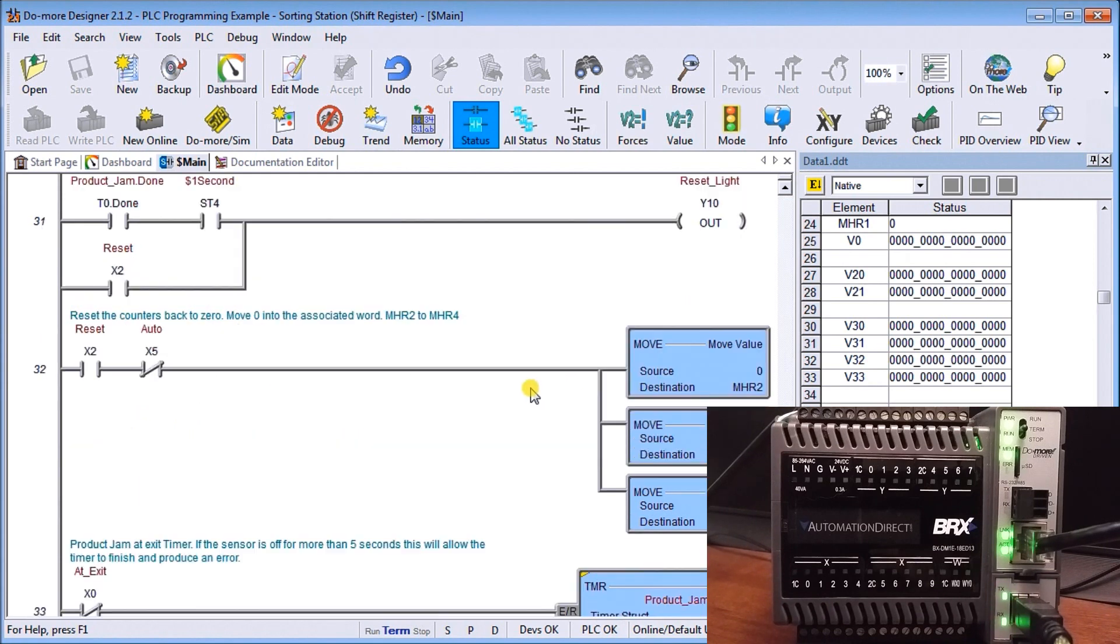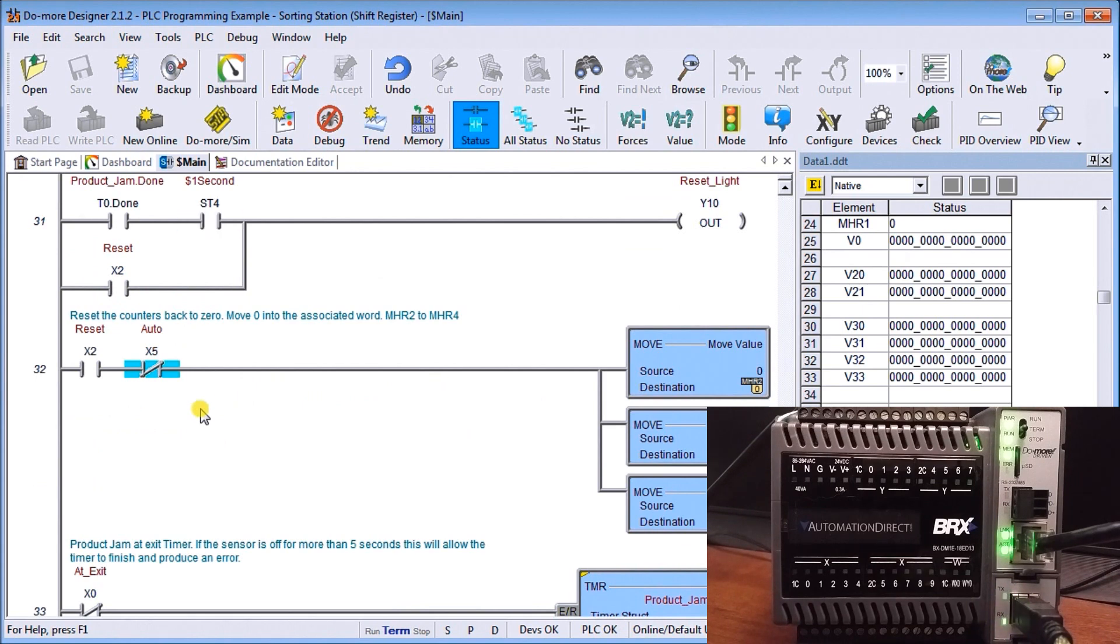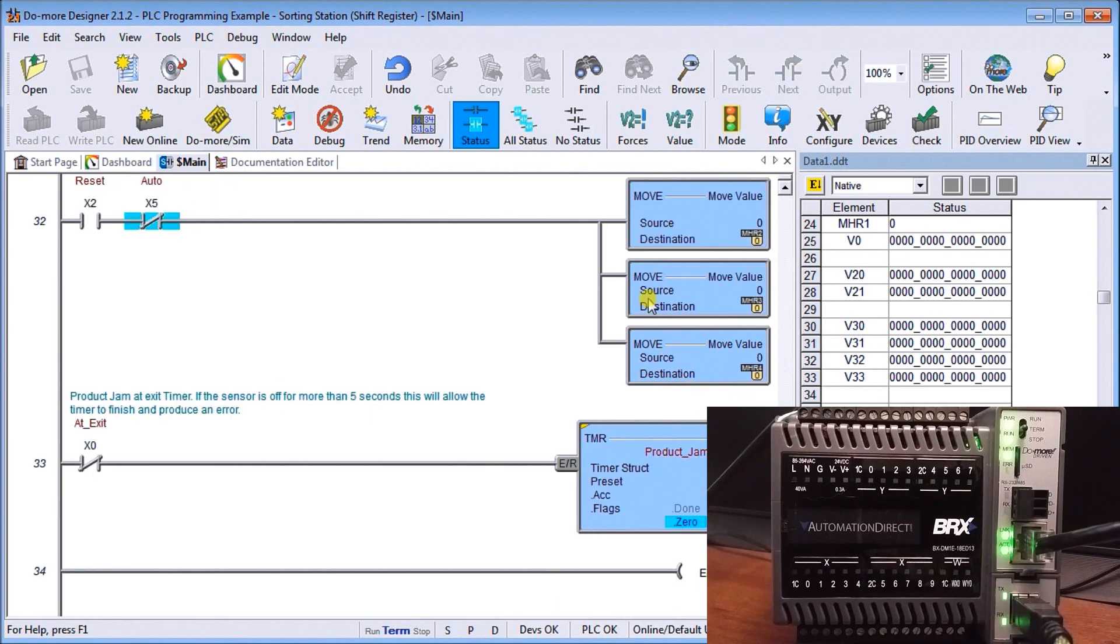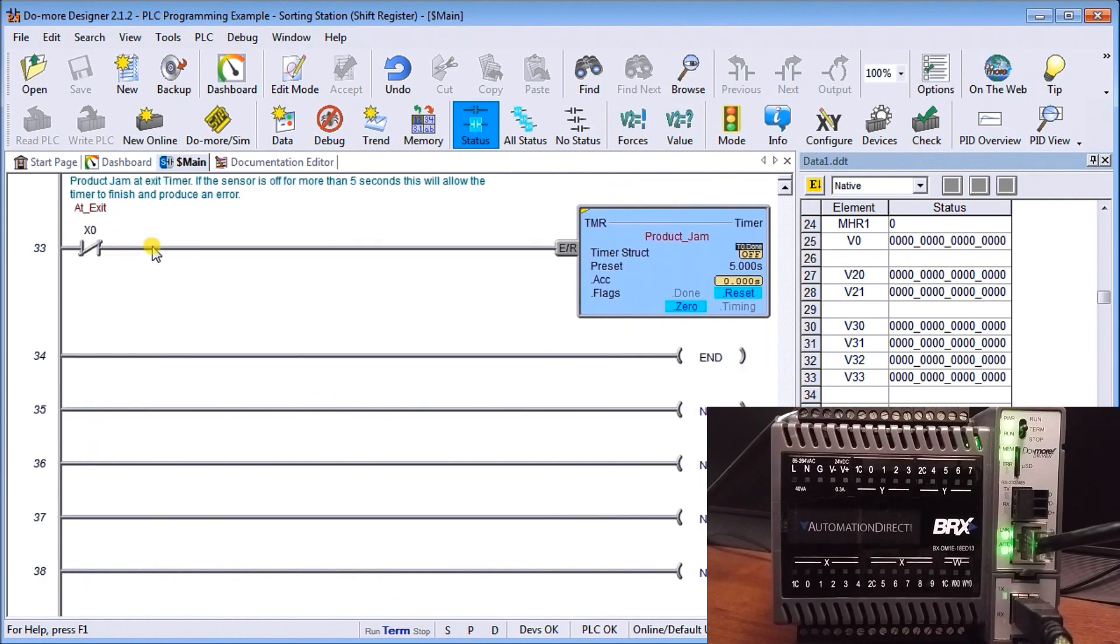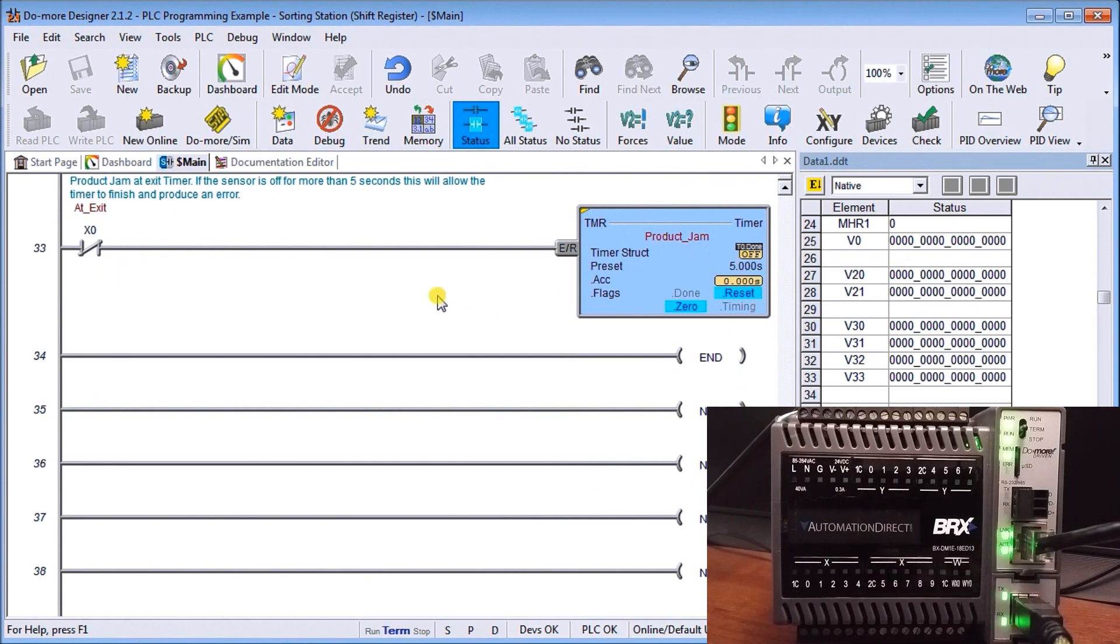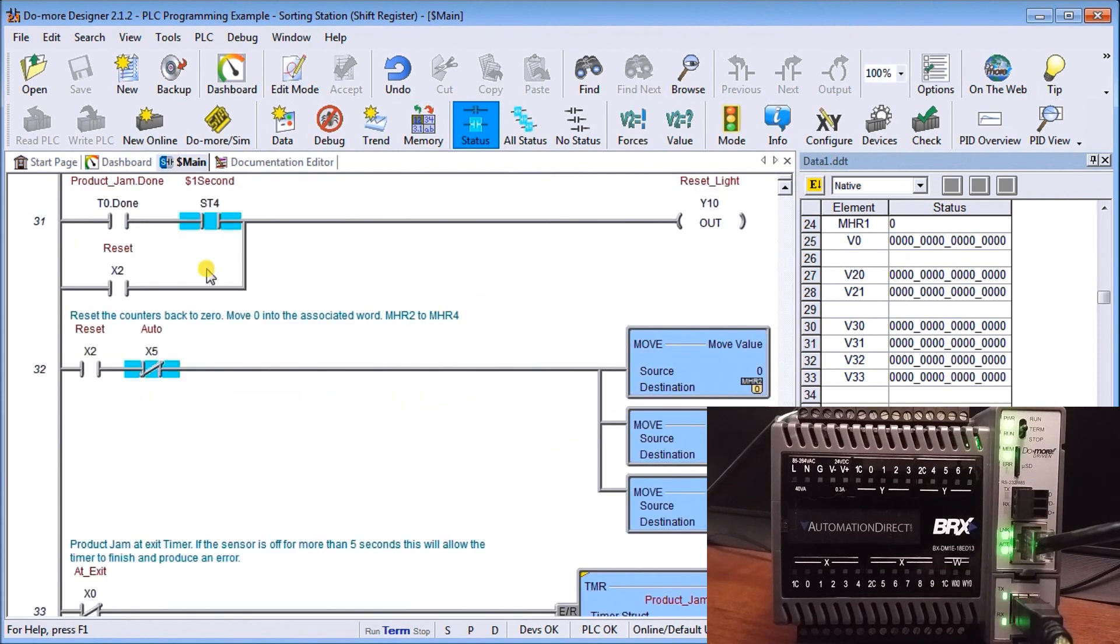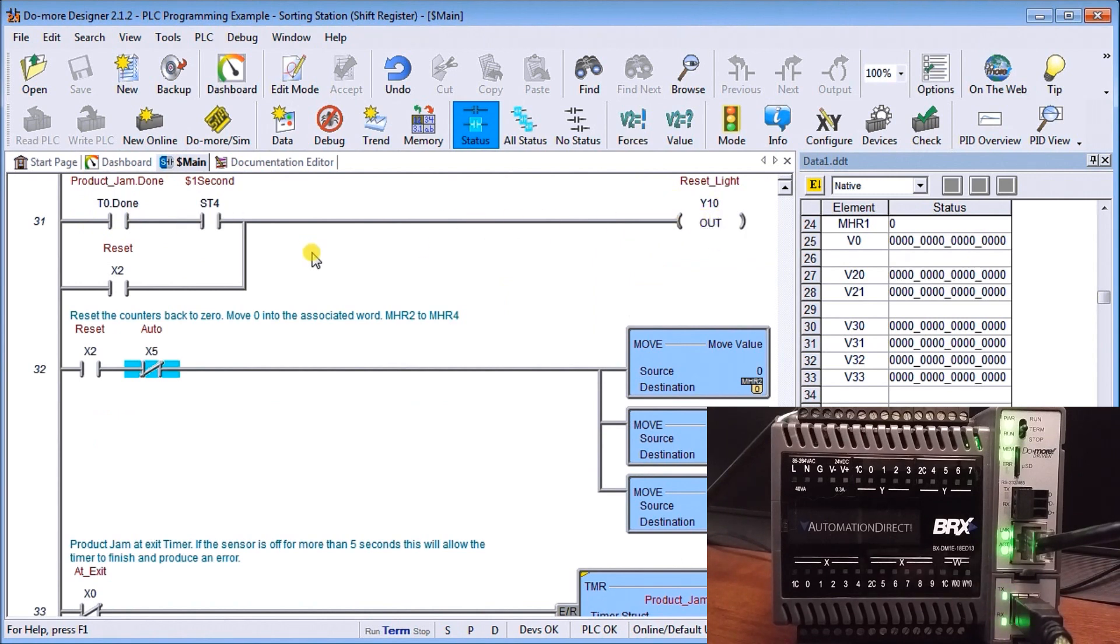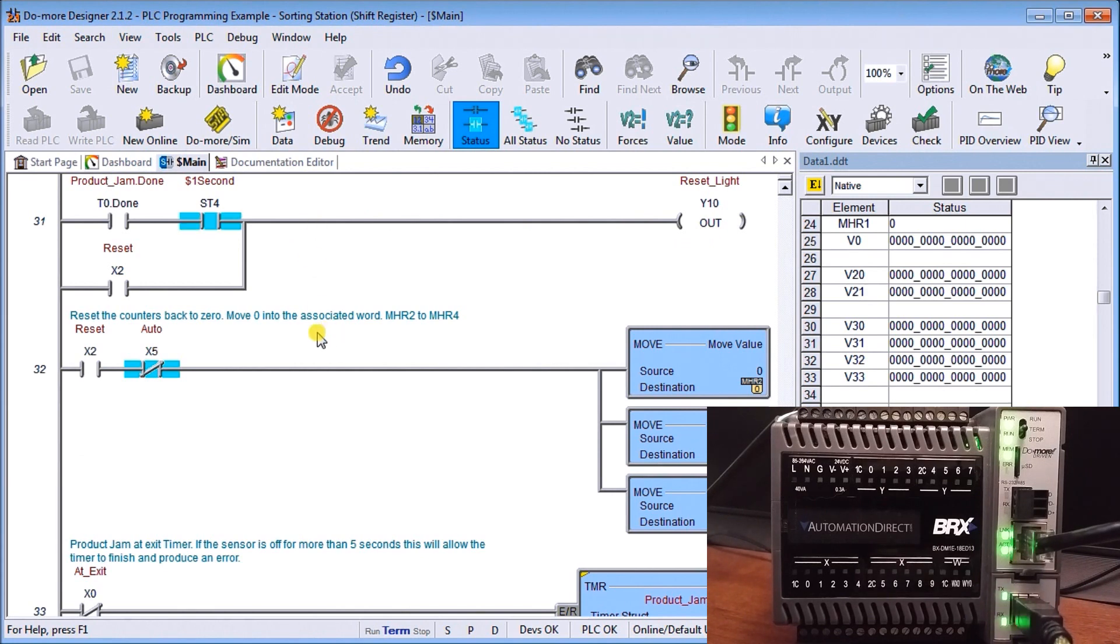We have our reset counters, and those counters move zero into the output value. We have our product jam. At the exit sensor, if it doesn't see it for more than five seconds, this timer will time up, which then starts our product jam sequence, which flashes our reset light and stops our latching circuit that we had previously.